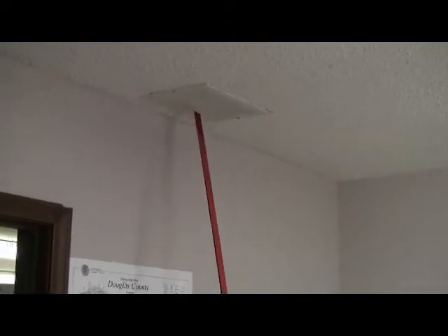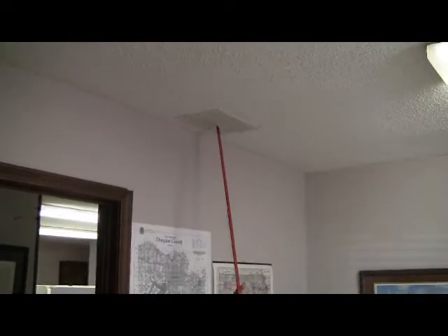This is the return duct in the ceiling, and we've got enough leakage that we're actually pulling air from outside through the ducting system and into the building, using the blower door. The furnace system is not operating at all. This is just pressure caused by a fan that's blowing air out through the front door of the building, sucking air in from leaks in the ducting system.